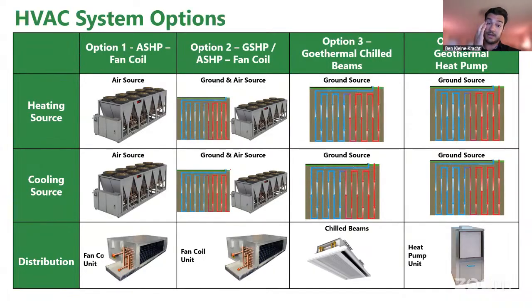Lastly, or I guess not lastly, options 3 and 4 are both geothermal. The terminal equipment is really the difference between the 2. For chilled beams, we would be using, again, a 4-pipe system that's pumped from the mechanical room, from the well field, to chilled beam diffusers. So these chilled beams are like lay-in tiles, or they can go in exposed ceilings, either one. And they have 4-pipe connections. And this diffuser would provide the heating and the cooling directly at the ceiling space.